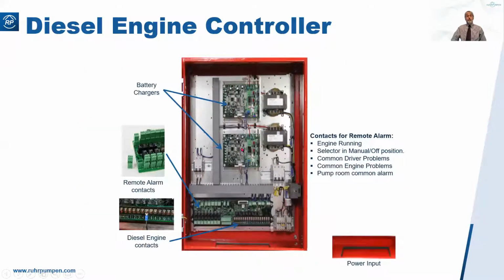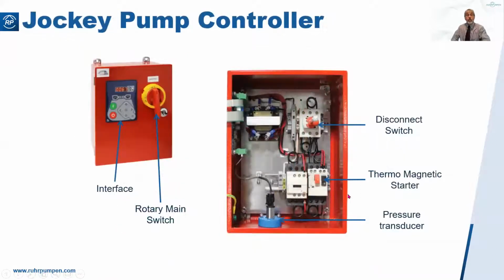2 battery chargers, 1 for each one. Remote alarm contacts for these remote alarms, and these are the wiring contacts here at the bottom to the diesel engine. Jockey pump panel. As I mentioned earlier, jockey pumps are not regulated by NFPA-20, but they do need to have a listed jockey pump panel with a pressure transducer to automatically start them.